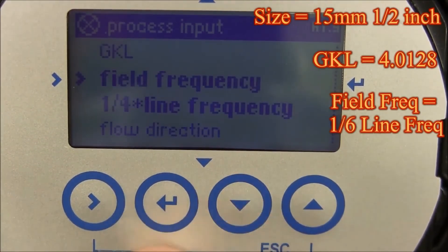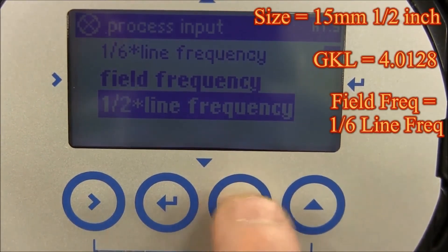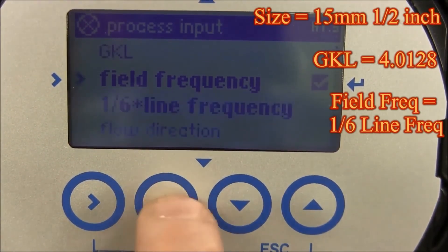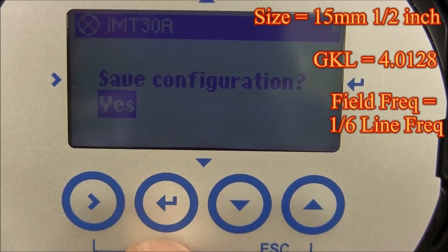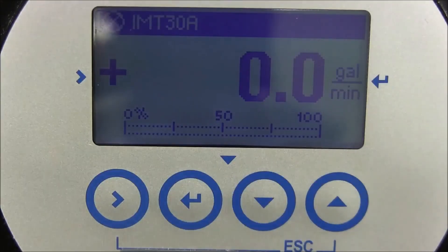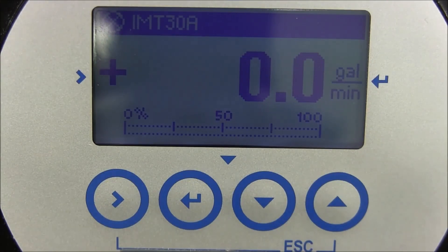Use the down arrow to go to field frequency, then hit the right arrow. Go up or down until you see one-sixth line frequency, then hit the enter key. Continue to hit the enter key until you see save configuration. With yes highlighted, hit enter to save your data. You have now finished entering in the analog output measurement and process input data into an IMT30A transmitter.